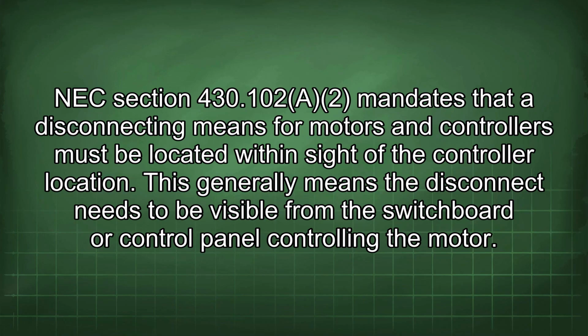NEC Section 430.102(A)(2) mandates that a disconnecting means for motors and controllers must be located within sight of the controller location. This generally means that the disconnect needs to be visible from the switchboard or control panel controlling the motor.